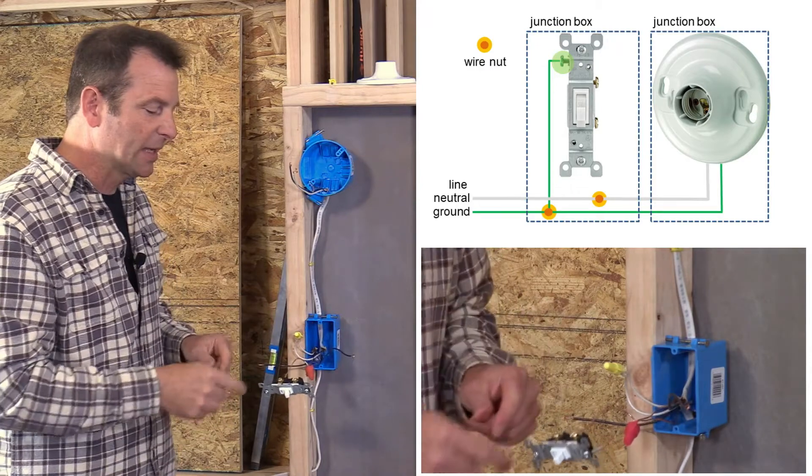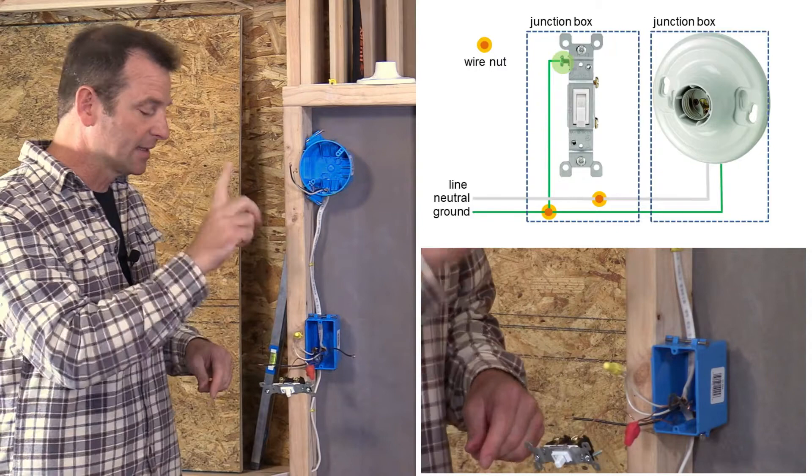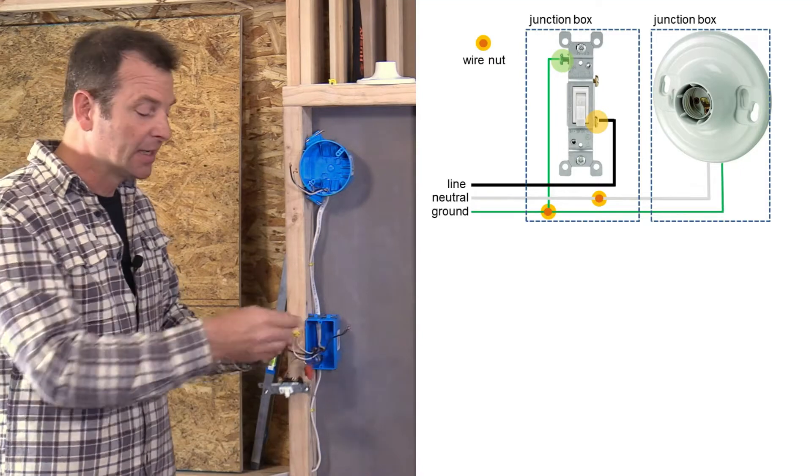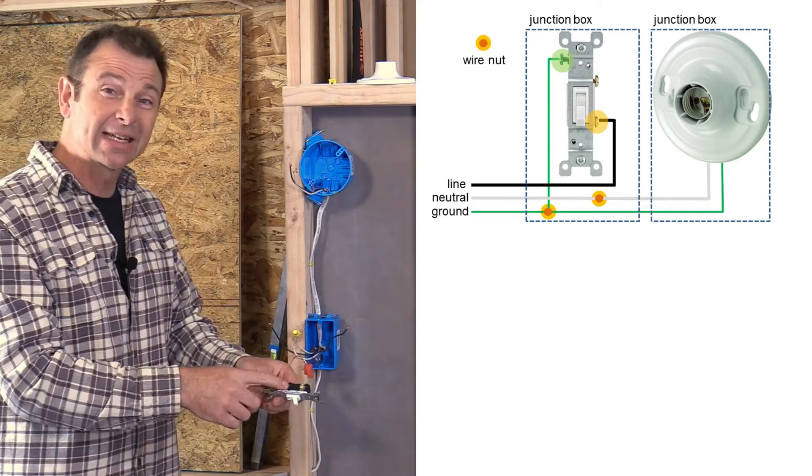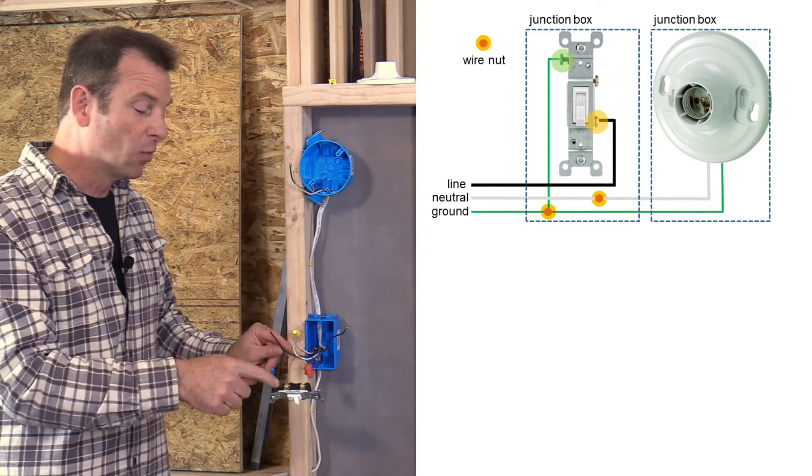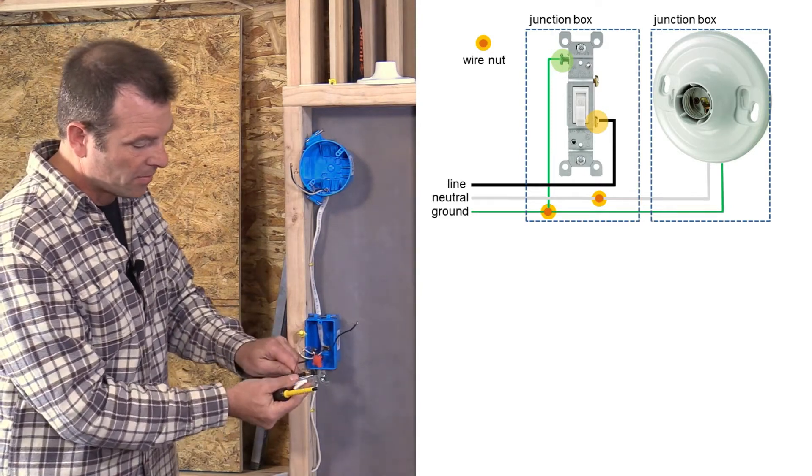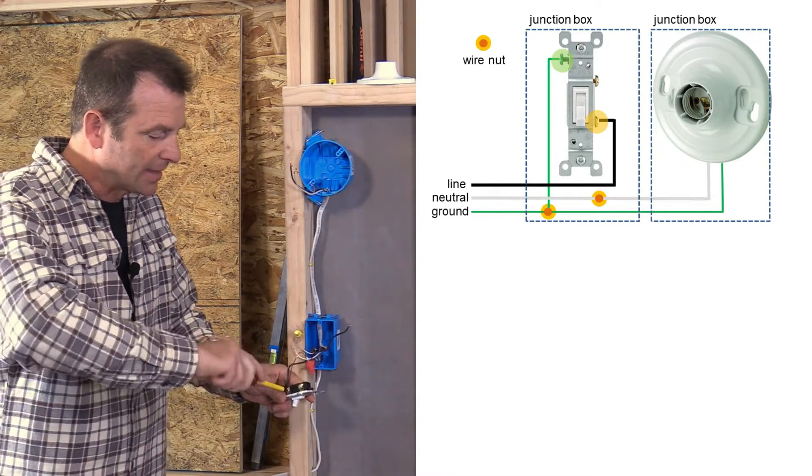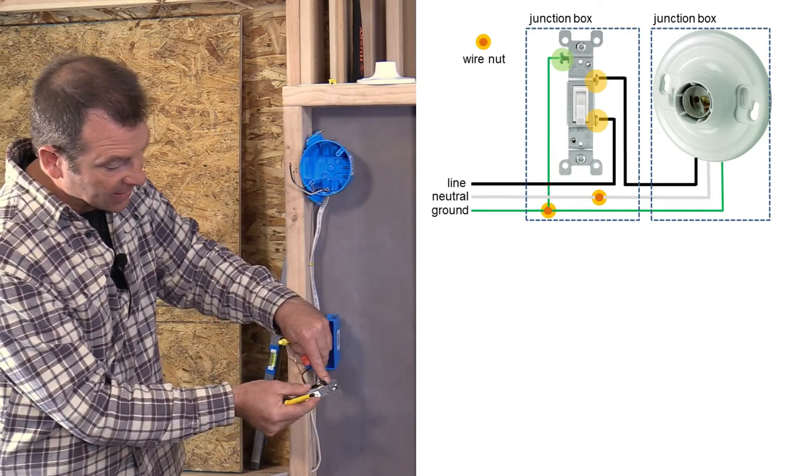So phase two is complete for the switch. I have my ground with my pigtail. And then I have my neutral wires connected that bypass my switch. Now I have two hot wires, black wires left. I have two terminals on this switch. So each one of these black wires is going to get connected to my single pole switch. And it does not matter which terminal goes where. So we just need one connection for each wire. So I'm going to connect this wire here. Make a nice tight turn on that screw. And then my other wire is going to connect to the other terminal.